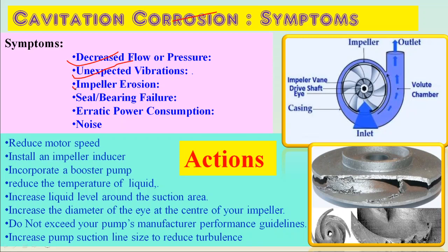You can see impeller erosion, the size of the impeller gets reduced, and the pump will not function well. You will see lots of bearing and seal failures. Then erratic power consumption, the pump needs lots of power, which is also a sign that cavitation is happening. And the last one is noise, you will hear lots of noise.